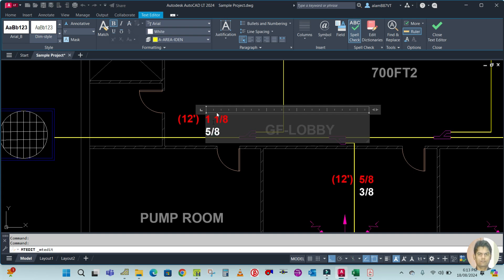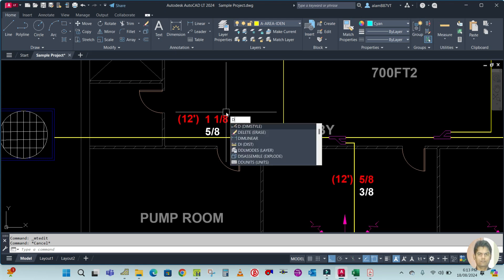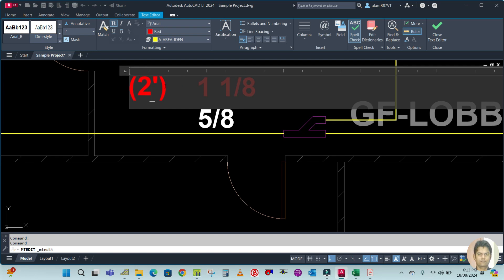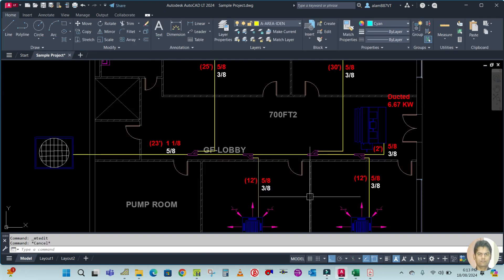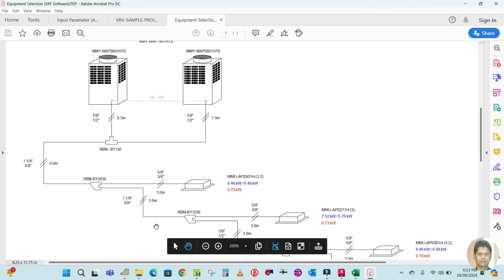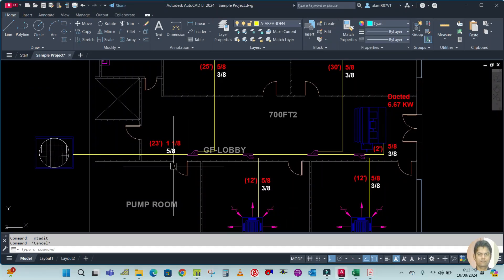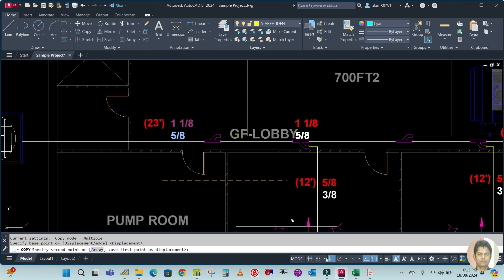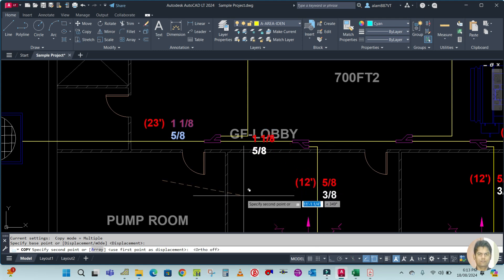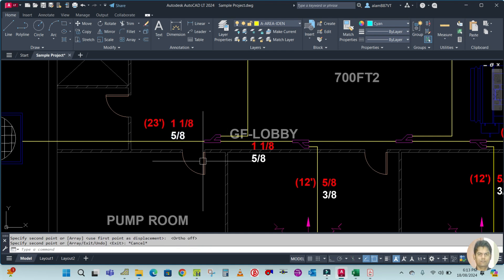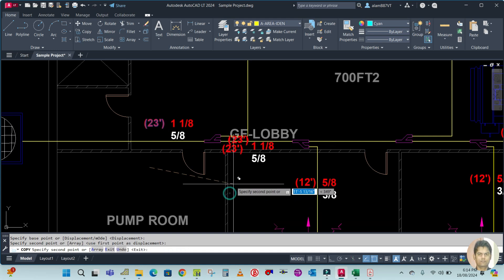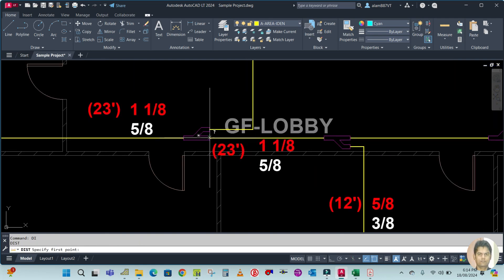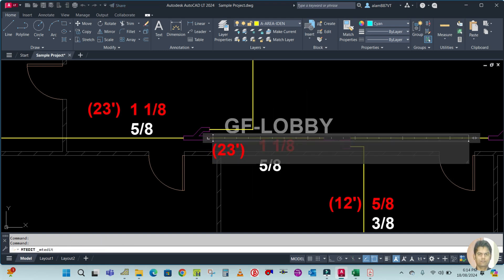The pipe size is 5/8 by 5/8. Measure the pipe length using DI from here to here — 23 feet. Then from this ref-net to the next ref-net, also update: pipe size 1-1/8 by 5/8. Copy this and place it here and here. The pipe length from ref-net to ref-net is 9 feet.